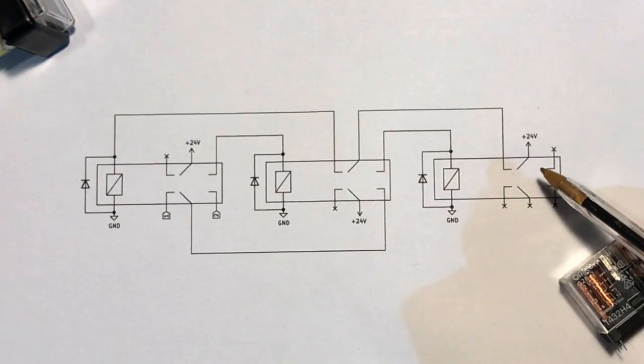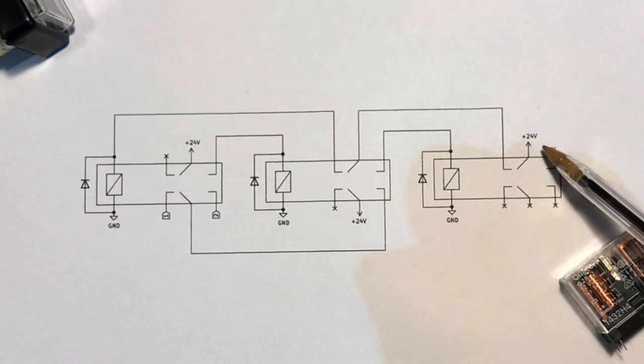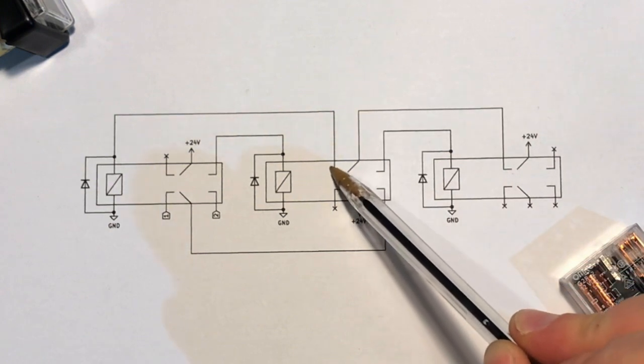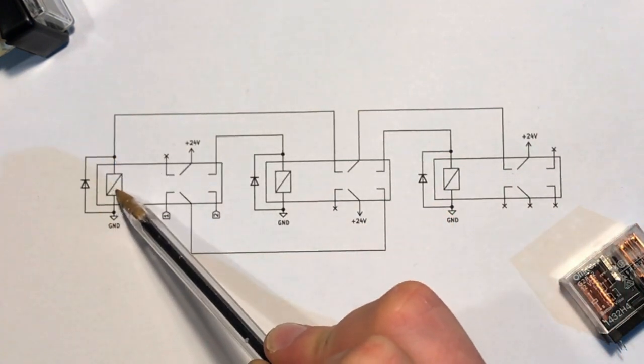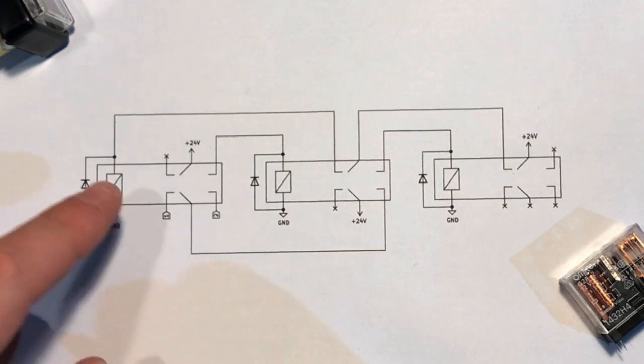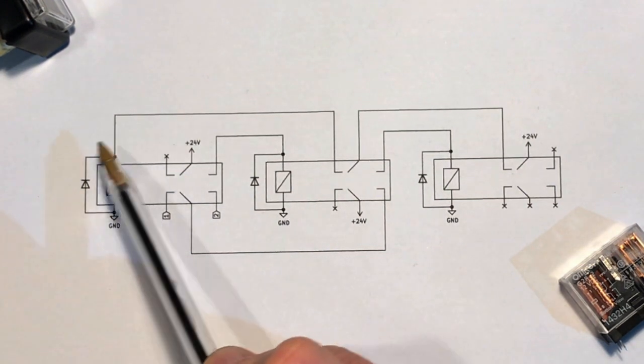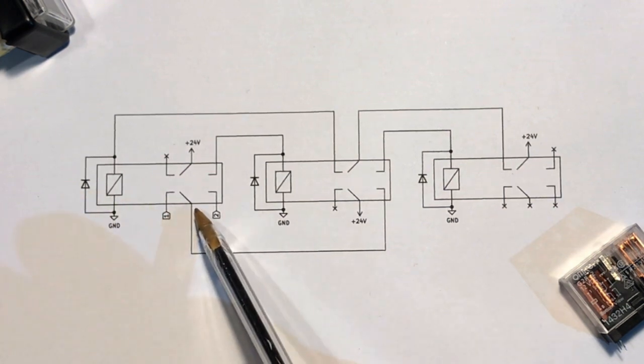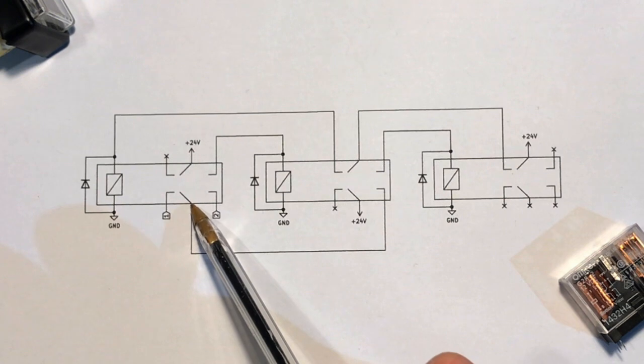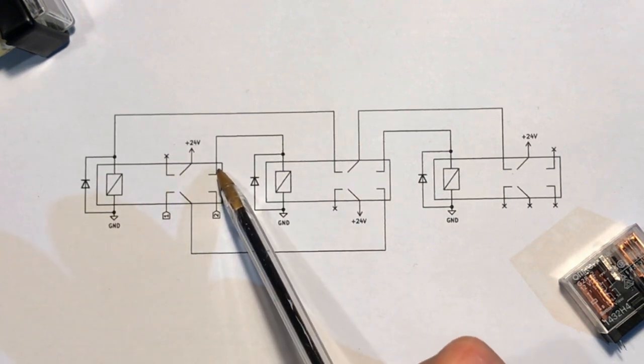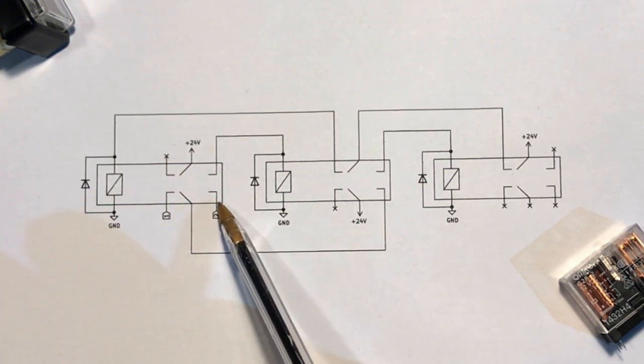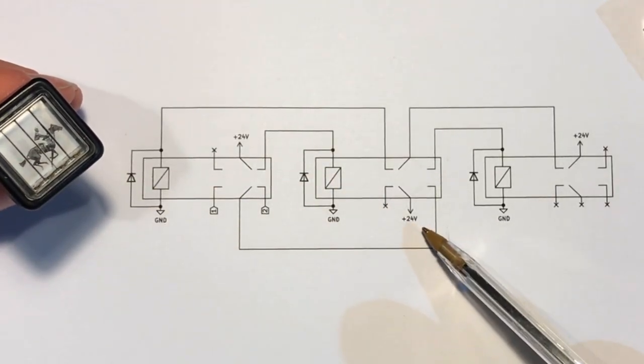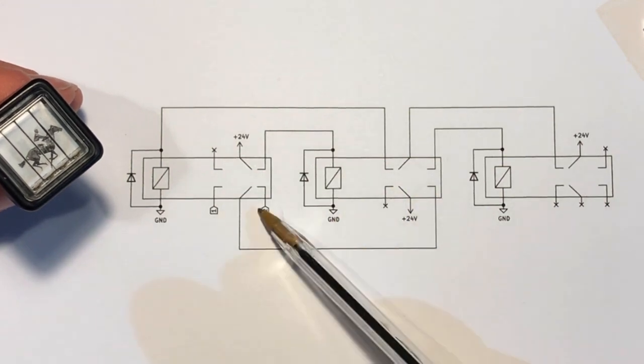Now let's have a look at how the power is being switched to the coils. You've got 24 volts coming in here, it's connected through here, going through this switch here, back out and eventually into the coil of this relay. Now because of that capacitor that we've got connected across the coil it's going to take a little while to turn on. But once it does it's going to cause these middle terminals to switch over and contact the normally open terminals. And as far as the indicator is concerned nothing has changed because power is still not being connected through the switch here to pin two.